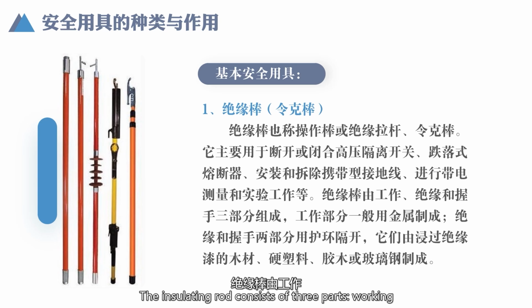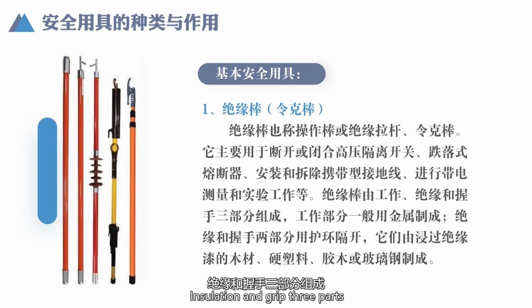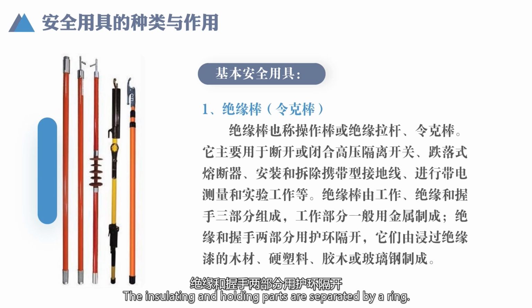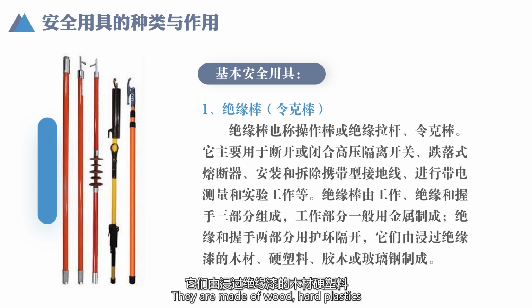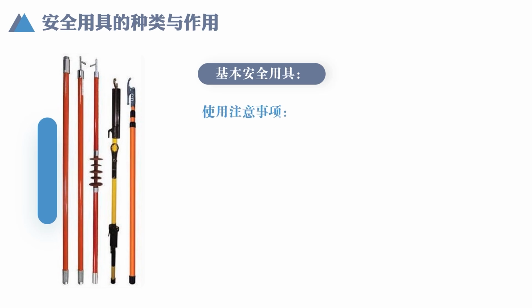The insulating rod consists of three parts: working, insulation, and grip. The working part is generally made of metal. The insulating and holding part are separated by a ring. They are made of wood, hard plastics, impregnated with insulating varnish, glued wood, or fiberglass.